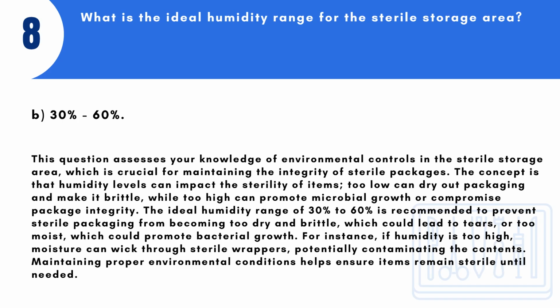Answer: B. 30% to 60%. This question assesses knowledge of environmental controls in the sterile storage area, which is crucial for maintaining the integrity of sterile packages. The concept is that humidity levels can impact the sterility of items. Too low can dry out packaging and make it brittle, while too high can promote microbial growth or compromise package integrity. The ideal humidity range of 30% to 60% is recommended to prevent sterile packaging from becoming too dry and brittle, which could lead to tears, or too moist, which could promote bacterial growth.